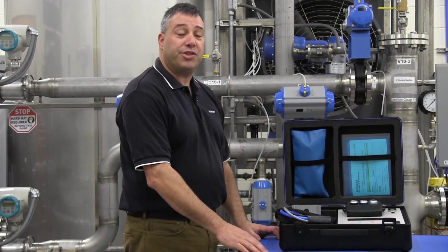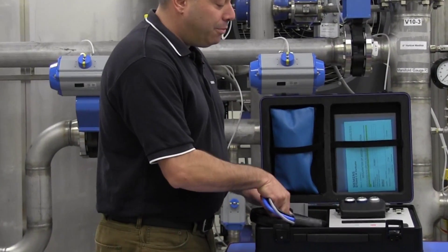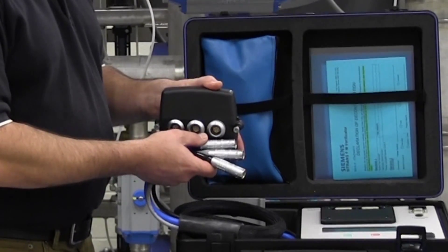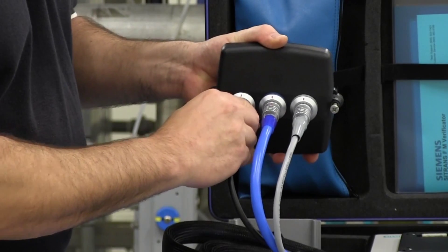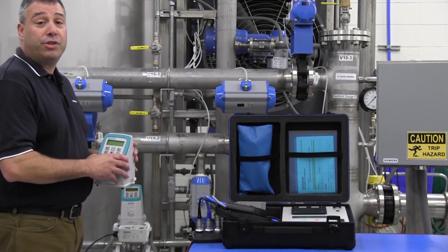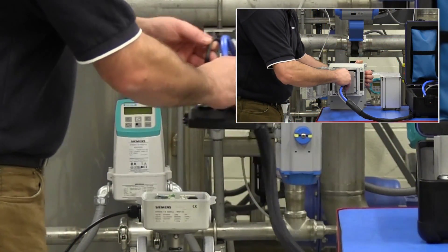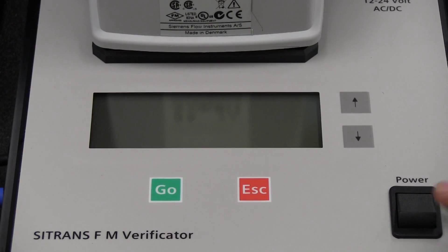Connecting the verificator to your flow meter is easy. First, disconnect power from your flow meter. Next, connect the cable assembly to the adapter appropriate for your flow meter. The cables are different but are color-coded and match similar color coding on the adapter for easy identification. Push the connectors straight onto the adapter until you hear a click. Next, remove your transmitter from either the flow tube or, if your transmitter is remote, from the remote wall bracket or enclosure and carefully place the transmitter on the verificator and push firmly to seat. The adapter and cable assembly should then be installed in place of the transmitter.